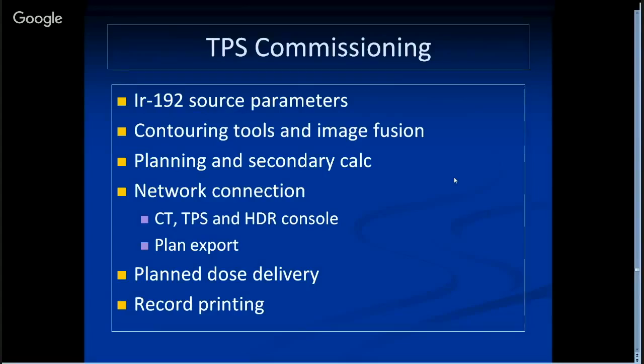You need to make sure the network connection is good, from the CT to your planning system, so you can send a CT image to the planning system and do planning with that image. Then you send that plan to the HDR console, and you may do a delivery according to the plan. You check the record and print it to confirm it's correct. All this stuff you need to make sure.